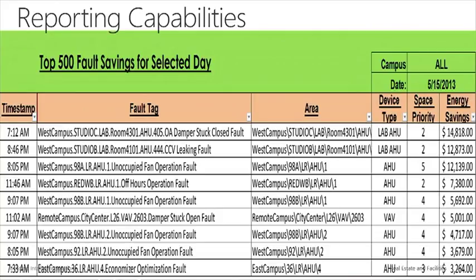So what you're seeing here is moments in time and being able to have this awareness that we never had before. And that's good, and it's wonderful. And it's lowering our energy costs by 6 to 10%, and it's optimizing our campus. It's doing great. But there's other things that are even more beneficial, and I would say the reporting. So this is one of my favorite reports called the Top 500 Faults for a Given Day. It tells me when did it happen, what was the asset, what was the priority of the space, and how much does it cost me in wasted energy if I do nothing? And on this one, I prioritized it by cost, but we actually prioritize it by the priority of the space.